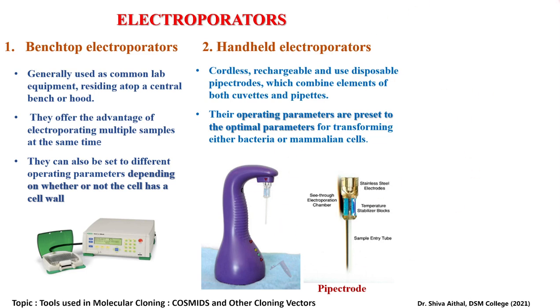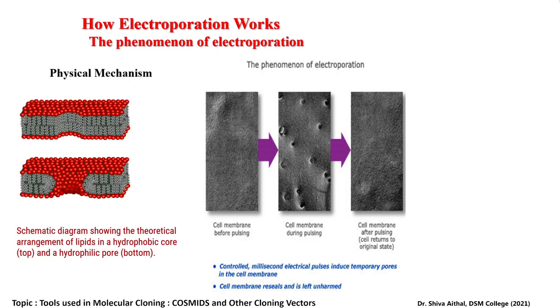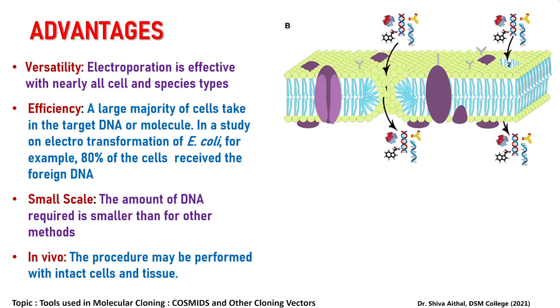Pipectrodes of the handheld electroporator can be introduced directly into small test tubes or Eppendorf tubes containing your samples, making them very effective and handy for rapid methods. Electroporation works by a physical method — as you can see here in this real-time picture, a cell membrane before pulsing, a cell membrane during pulsing, and once the DNA is introduced inside, the cell membrane after pulsing returns back to its original state. Controlled millisecond electric pulses introduce temporary pores in the cell membrane, and if done skillfully, you can end up with a bacterial cell membrane which remains unharmed and intact as if nothing has happened.